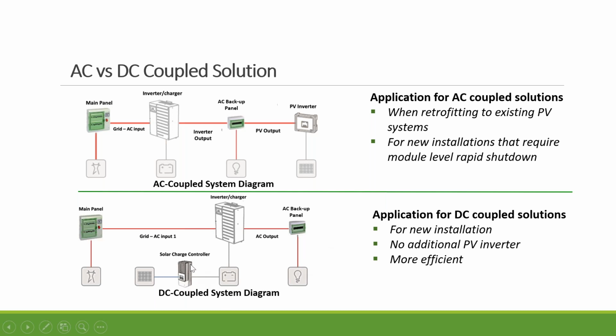Instead, you have a solar charge controller. This charge controller can be an external, separate device, or can also be combined in one unit with the hybrid inverter. The charge controller will take the PV and charge the battery, so it's DC to DC. The hybrid inverter connects to an AC backup load panel if you need it, and to the main panel.